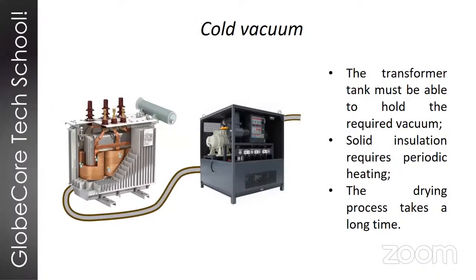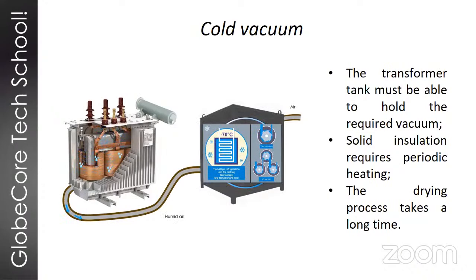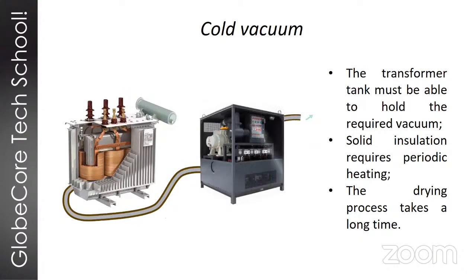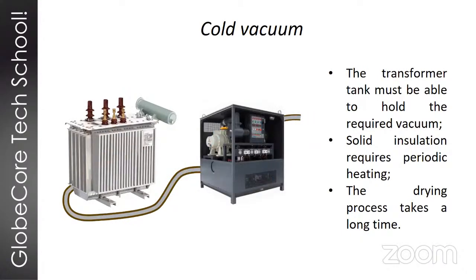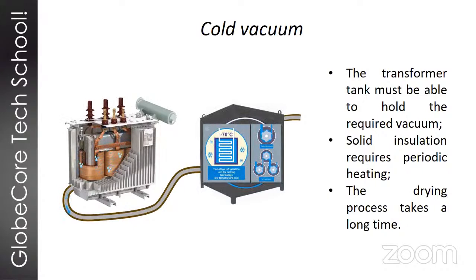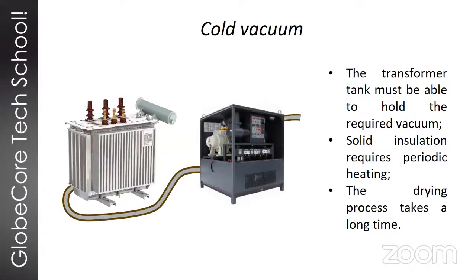All right, cold vacuum. Another clever process. This also involves heating of the transformer and a vacuum. The important condition here is that the temperature of insulation must not fall below 20 degrees Celsius. This method is implemented using a special cold trap that is designed to freeze out the water vapor. And this really increases the efficiency of vacuum pumps, and it allows us to extract the water vapor from the transformer tank quite quickly.